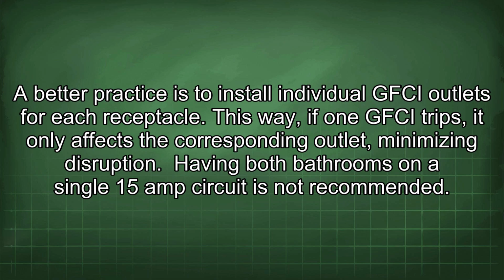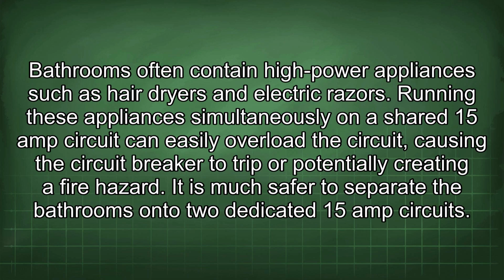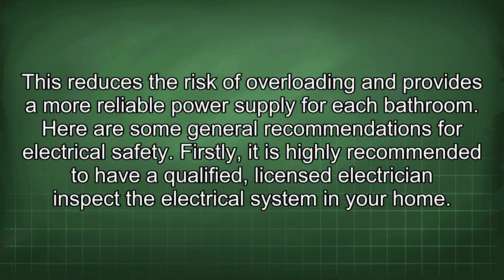Having both bathrooms on a single 15 amp circuit is not recommended. Bathrooms often contain high power appliances such as hair dryers and electric razors. Running these appliances simultaneously on a shared 15 amp circuit can easily overload the circuit, causing the circuit breaker to trip or potentially creating a fire hazard. It is much safer to separate the bathrooms onto two dedicated 15 amp circuits. This reduces the risk of overloading and provides a more reliable power supply for each bathroom.